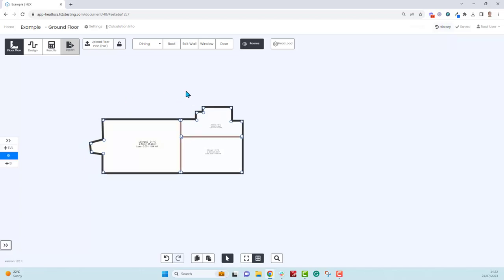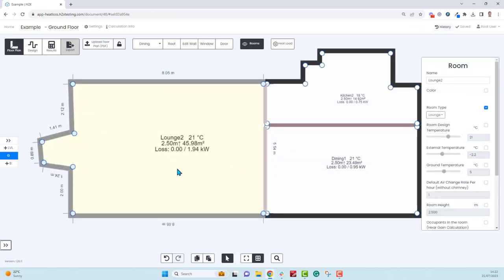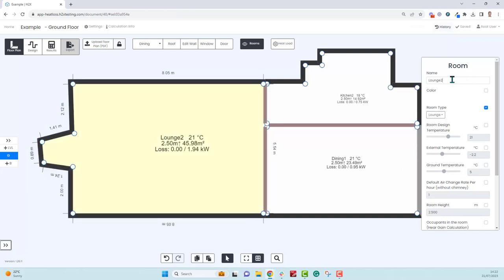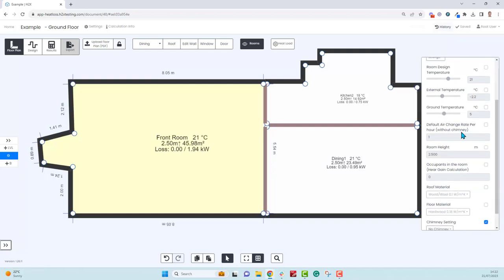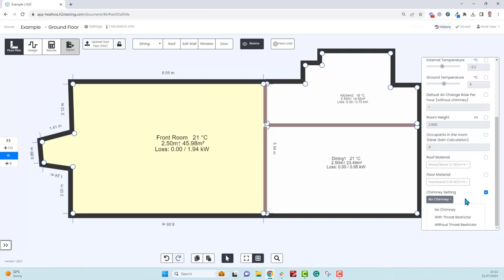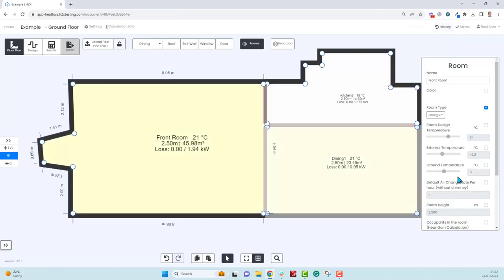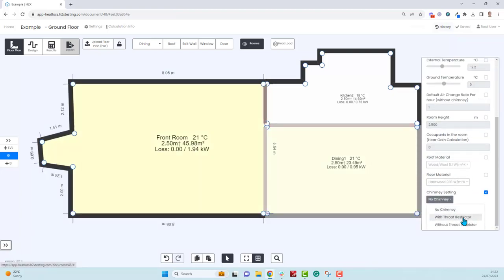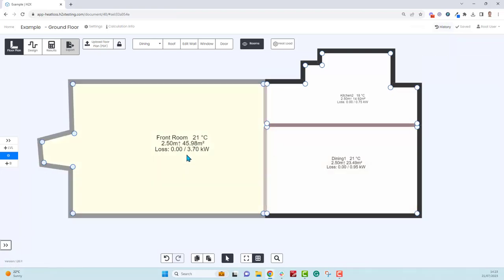You can keep going and drawing. Just to show you the properties, if we click on this lounge now, we can change the name so we could call it front room if we wanted to. We can change the temperatures that it's using for the calculations, we can override default air changes, the heights and the materials too. If there is a chimney we can choose to add that. As we're drawing the room the kilowatt load is being calculated. Let's say now it's 1.94. If we do add a chimney with a throat restrictor, straight away it's gone up to 3.7 because there's many more air changes per hour in that room.